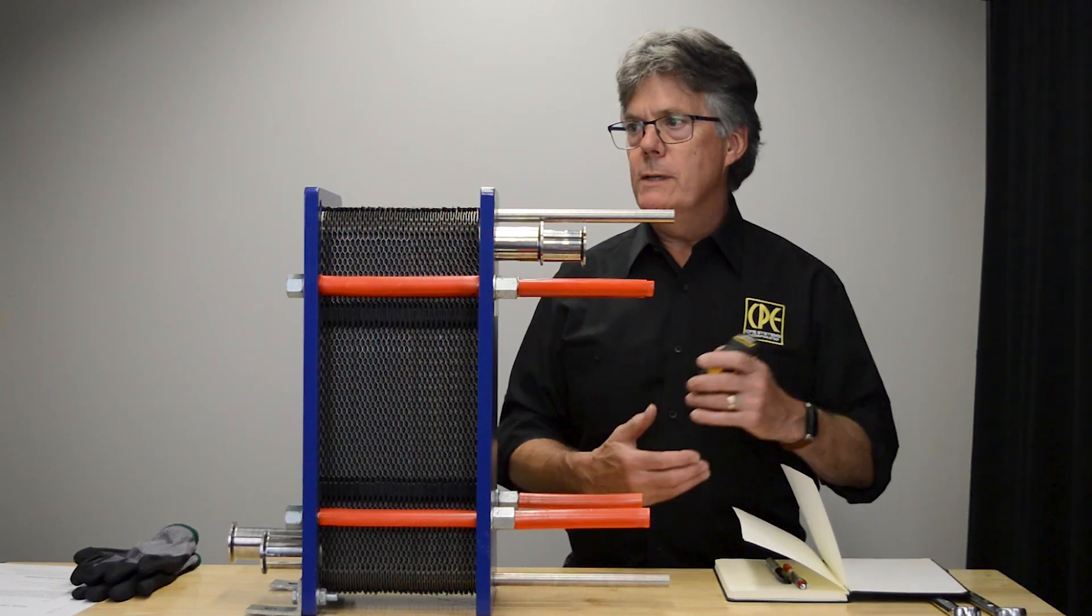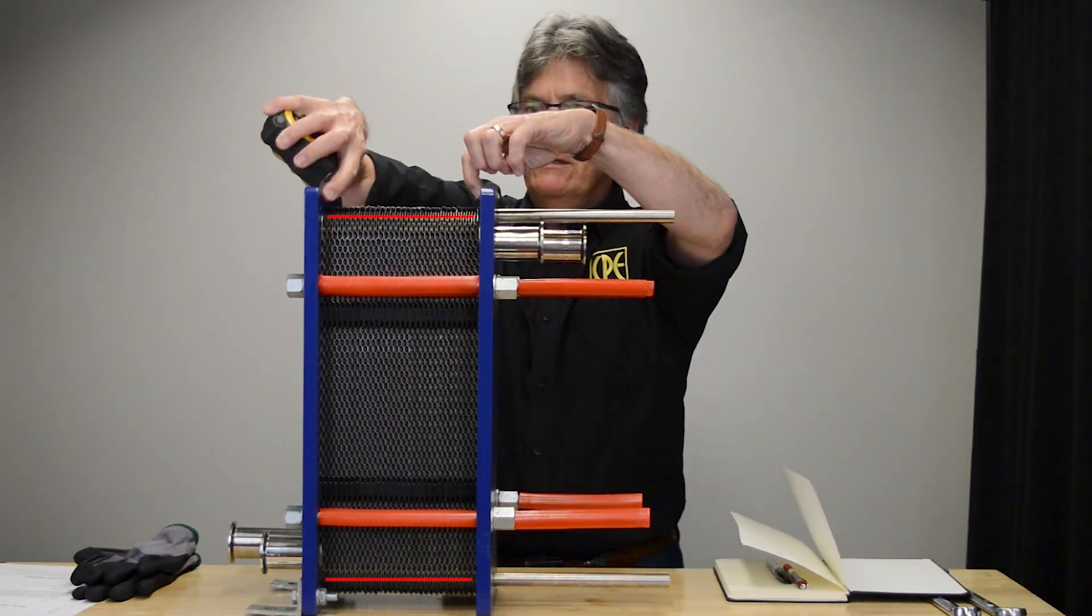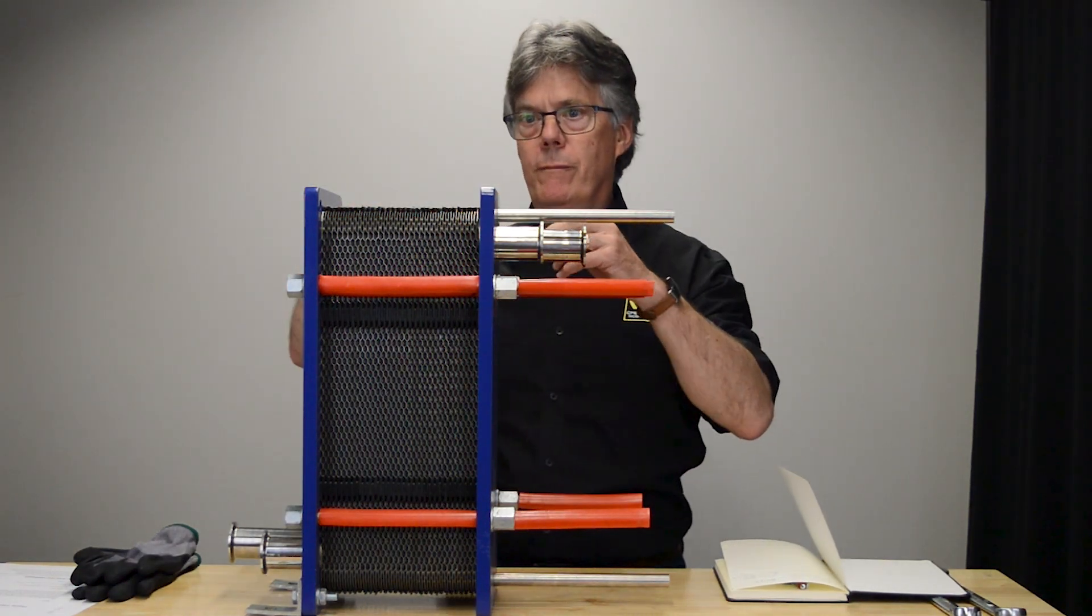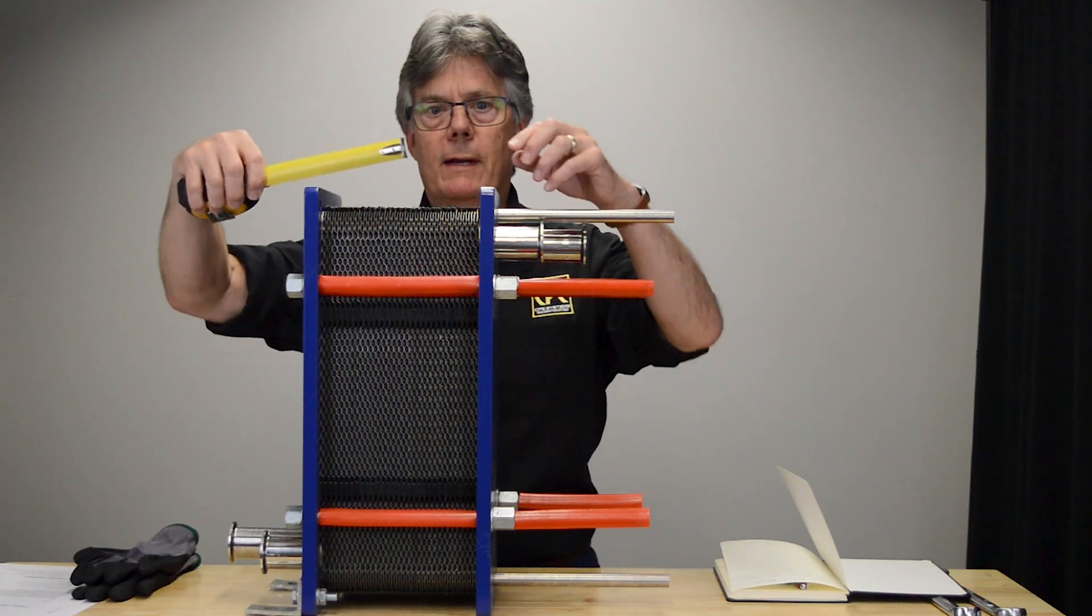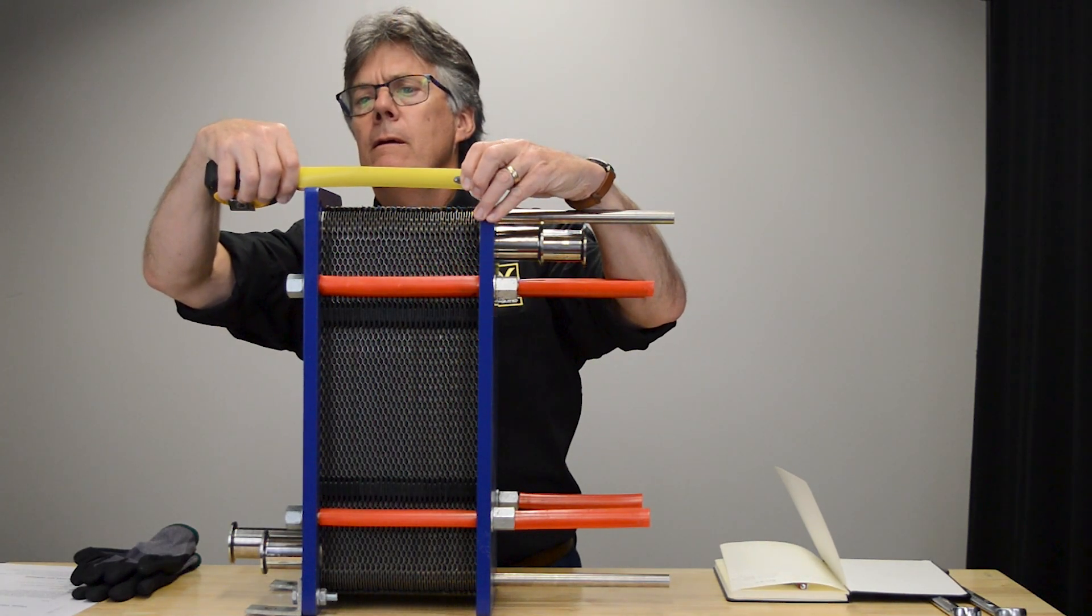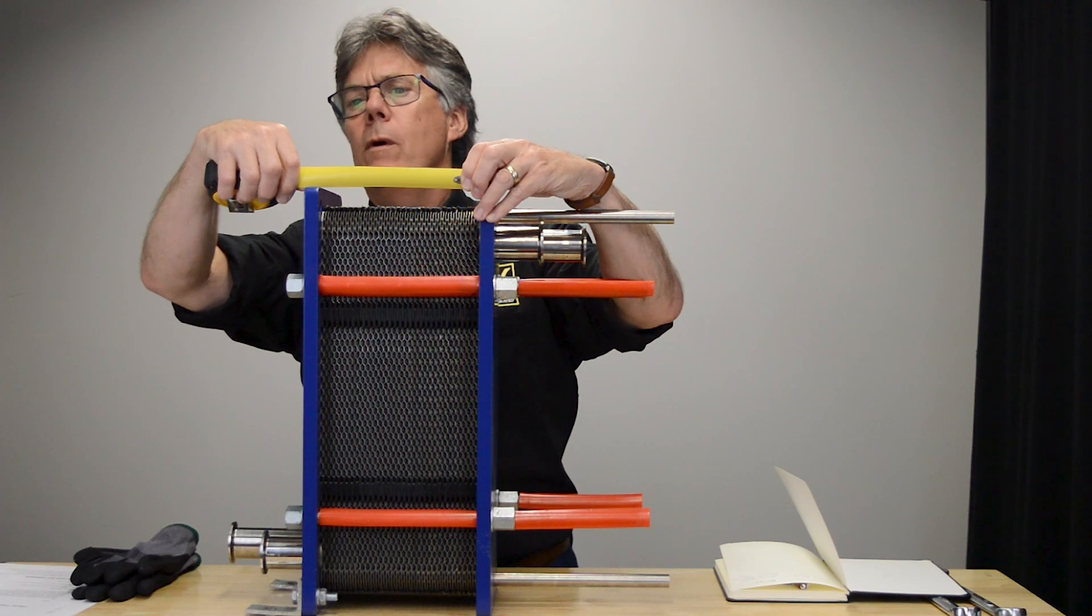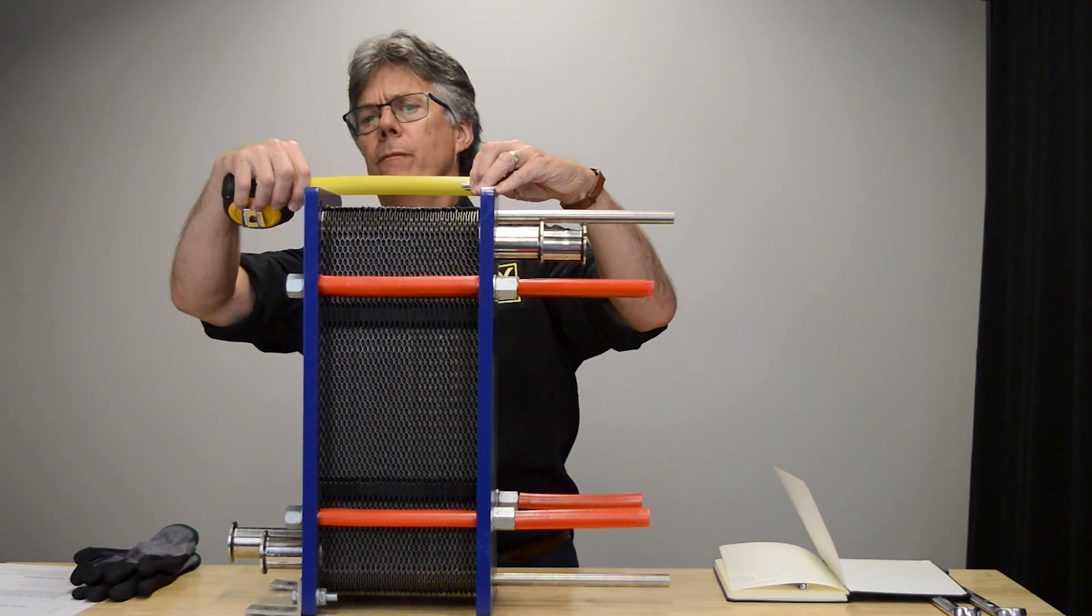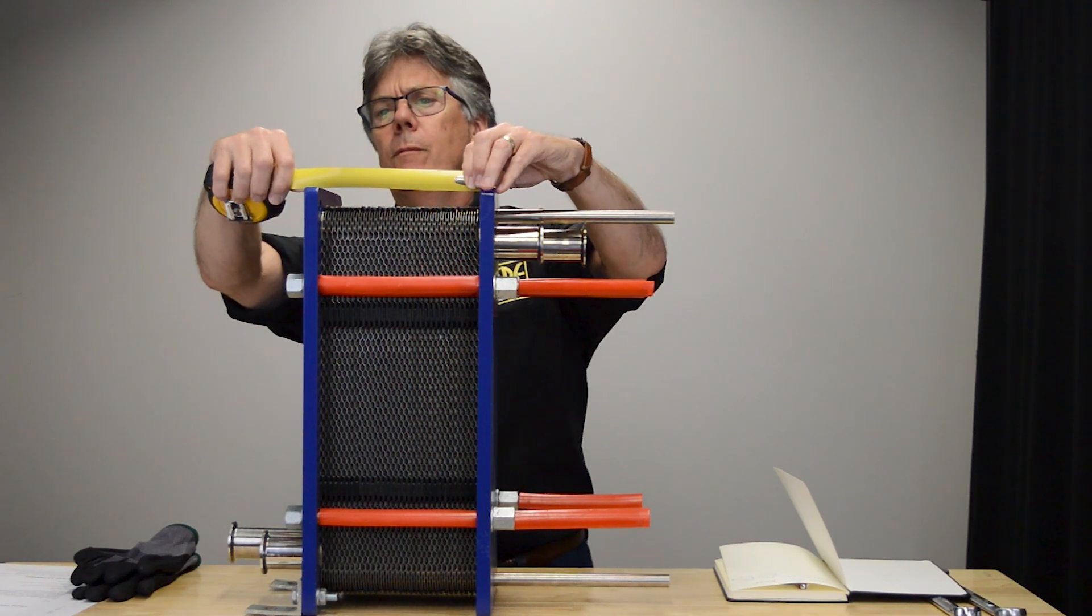The first thing I'm going to do before I take it apart is measure this distance in here, it's the A dimension. It's really important because you need to put it back to be exactly the same when you reassemble. So I'll just use my tape and it is 7 and 1/8 inches, 7.125 inches.